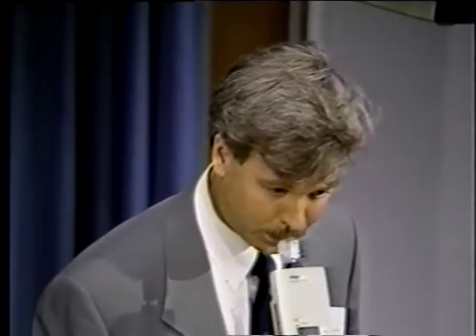The mouthpieces used will be spit trap mouthpieces, which will just be sealed and from different manufacturers, and you just blow into it. When I blow with enough pressure, you'll hear a tone come on, and after approximately 5 to 10 seconds, depending on how hard I blow, this device adjusts for how hard you blow. If you blow hard, it'll only require 5 seconds for the sample to be taken. If you blow soft, it'll require longer. So I'll just do my testing. The tone goes off when the sample has been accepted, and you see, if it's on the camera, that little P comes on, meaning a pass. So my blood alcohol is from 0 to 49.